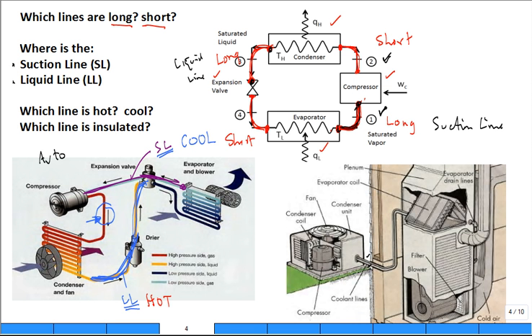Now, which one is insulated? Which of these lines are insulated? The suction line insulated or the liquid line insulated? The suction line is insulated. So why is the suction line insulated? Because as it goes through, it's cool enough that it would absorb some heat from the surroundings, but it's not going to help performance. And actually, if you bring in the cool refrigerant into the compressor, it keeps the compressor from getting so hot. So it's better to feed it saturated vapor that's not superheated vapor, relatively cool saturated vapor. It's good for the compressor to feed it saturated vapor, not liquid. Don't feed the compressor liquid. It'll break. But you don't want it to be superheated vapor. It actually provides cooling to that compressor.